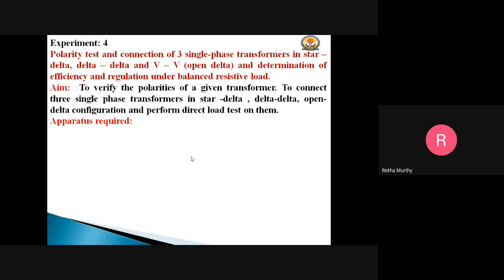In the polarity test there are two concepts: additive polarity and subtractive polarity. In additive polarity, we short the two primary ends - the P1 of one transformer is connected to the S1 of the other transformer. The other two ends left out, P2 and S2, are connected to the voltmeter.